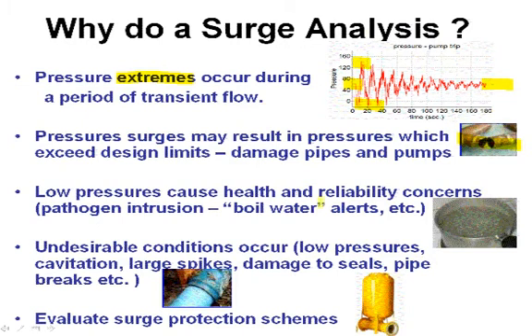These are considerations we have to be concerned about. They can result in broken pipes, as shown here, and damage to pumps. Low pressure will cause intrusion into your system — pathogen intrusion. You have to boil the water if you have a pipe break and you get negative pressures in your system. High pressures and low pressures both can damage seals, increase leakage, and shorten the lives of pipes.